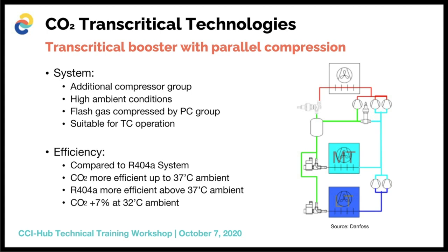Looking at the set point of 32 degrees Celsius ambient, you will find that CO2 can be up to 7% more efficient, and depending on the technology, the installation and the setup, sometimes even higher, but on average about 7% energy efficiency gain compared to a 404A system.